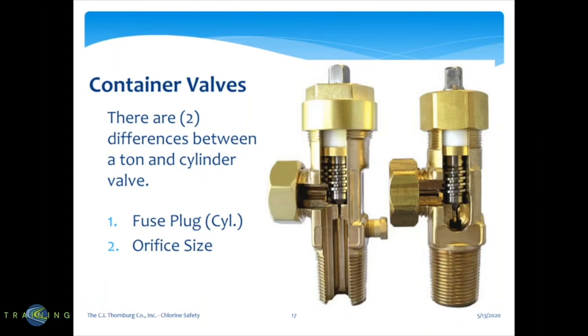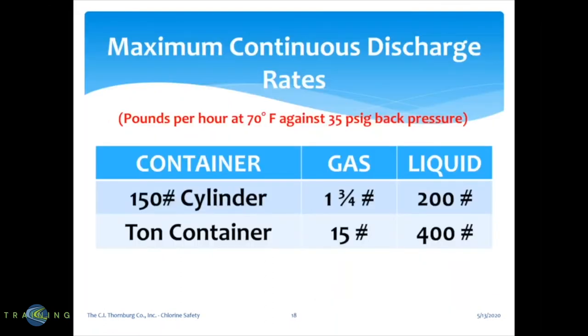Container valves. There are two differences between a ton and cylinder valve: the fuse plug in a cylinder and the orifice size. Maximum continuous discharge rates at 70 degrees ambient temperature with 35 PSI back pressure: for a 150-pound cylinder, the gas rate is 1.75 pounds per hour and as a liquid it's 200 pounds. A ton container is 15 pounds as a gas and 400 pounds as a liquid.